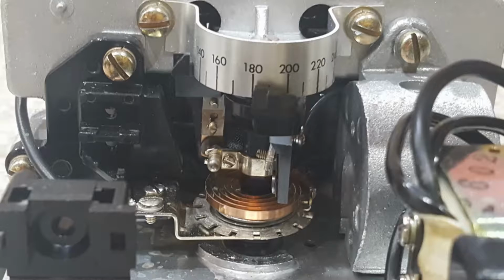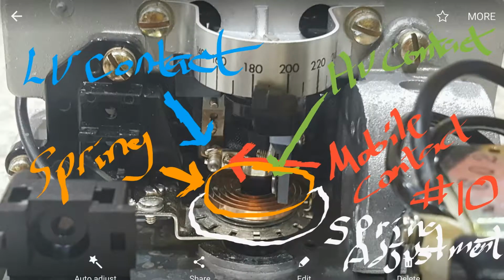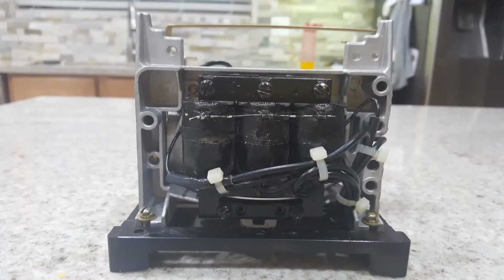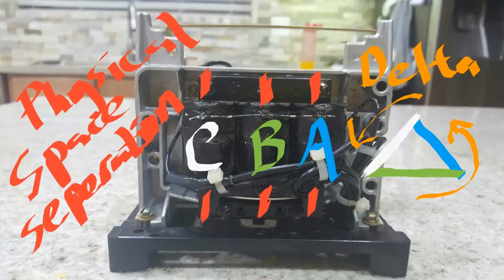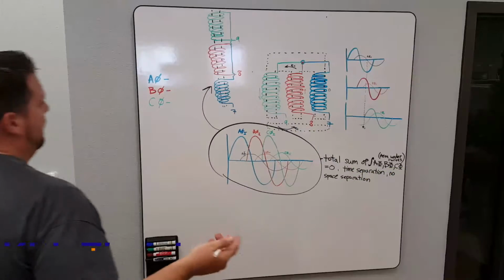On to the inner workings of the relay, we can see the coil spring, its respective adjustment, the mobile contact, the high voltage and low voltage contacts, with the spring being the primary adjustment for the high voltage pickup. Located on the back of the relay, we can see the E-type laminated structure with the coil on each leg. Input into this relay is a delta connection, although a Y connection is formed by connecting one lead of each coil together. Let's take a look at what makes the induction disc turn.